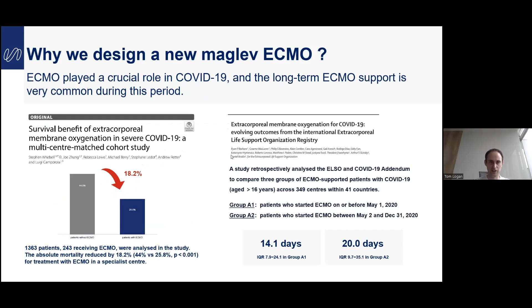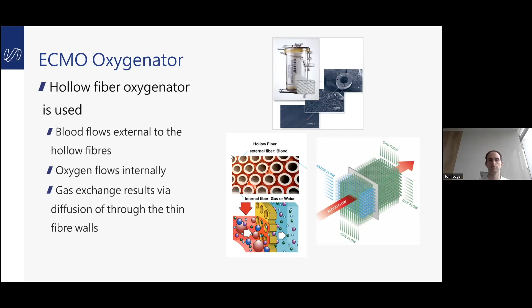So just a little bit of an introduction to the technology. The ECMO system is based around a hollow fiber oxygenator. In this type of system, the product consists of a whole load of very little fibers, little tubes, basically, and we pass blood externally around the tubes and oxygen through the middle of the tubes, and we have gas exchange across the tube to oxygenate the blood and to remove the carbon dioxide from the blood. And also within the design, we have other paths to pass hot water to keep the blood temperature managed.